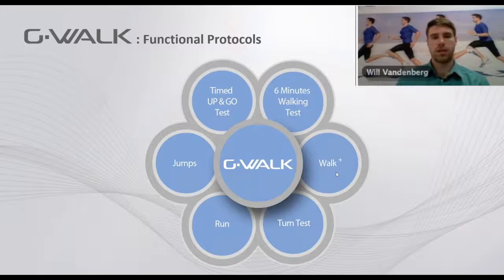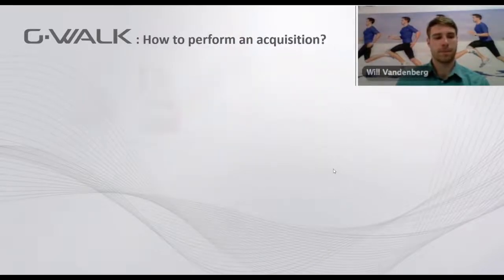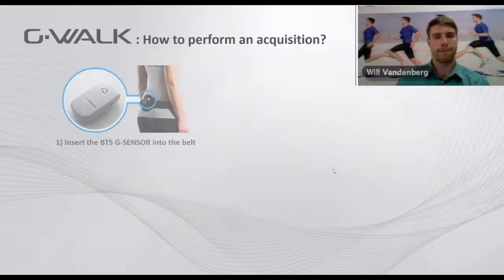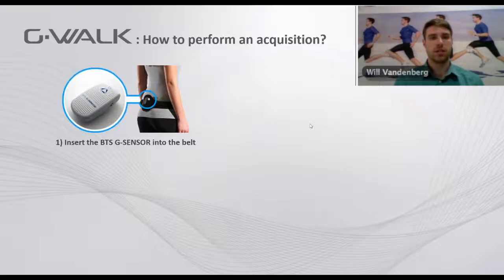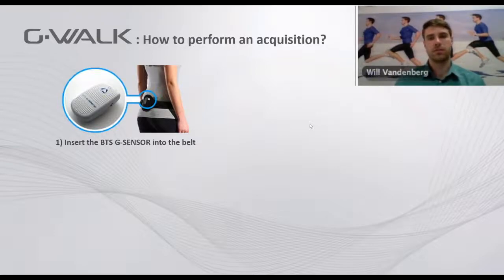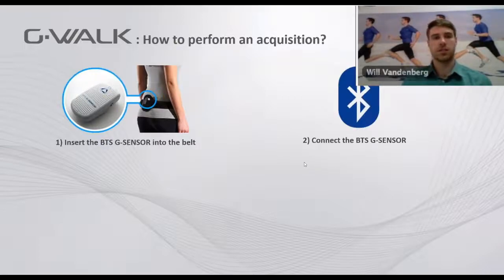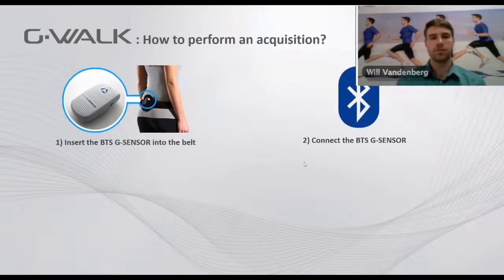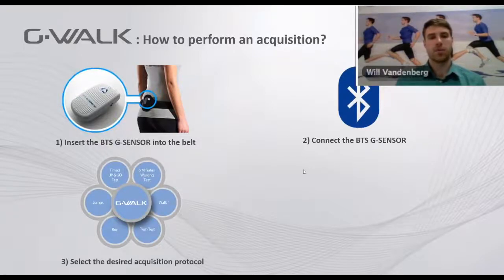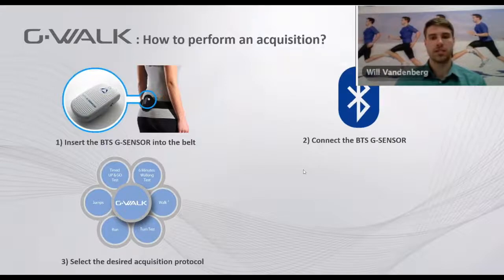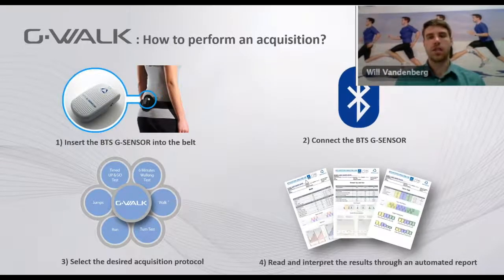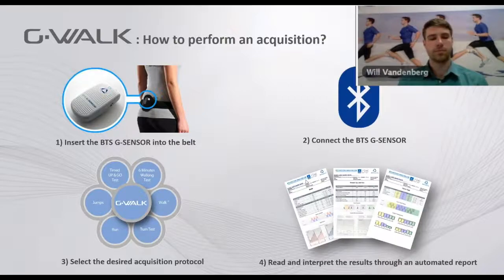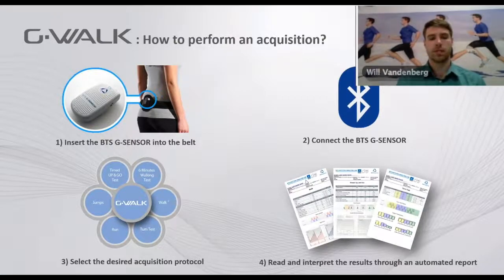To perform the test, you would first insert the G sensor into the belt which is placed on the back of the patient. You would then connect the G sensor to the computer via Bluetooth and then select the desired protocol and perform the test to generate the automatic clinical report. As you can see, it's a simple process to use the system.